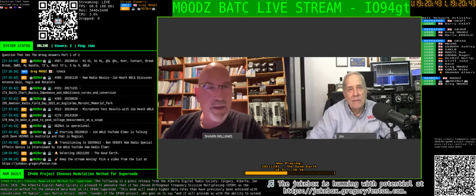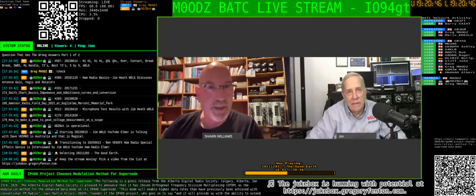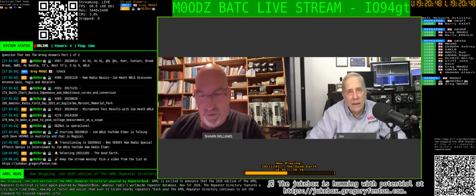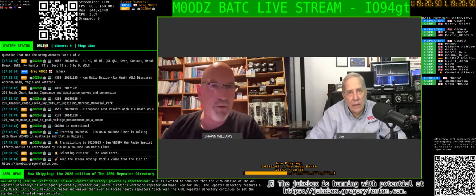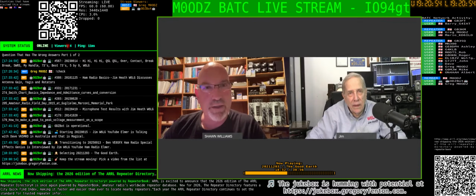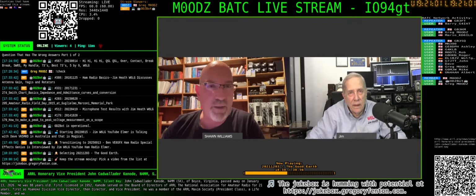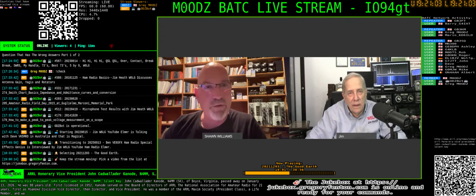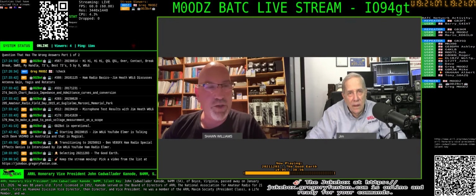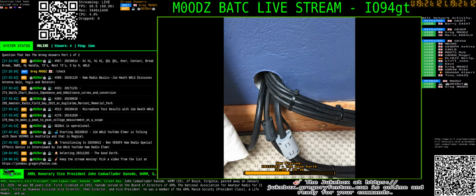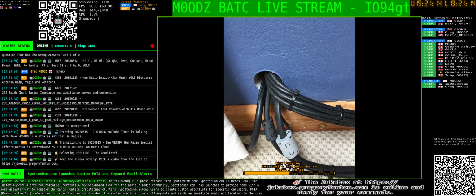But my neighbor's right next to me, and they're all around. So if I'm sharing their ground rod and their earthing system in their house, and it's coupled to my station, it's going to cause problems. So in my station, I have a 150 millimeter squared conductor, which is what I call my main RF earth. Everything bonds to that point.